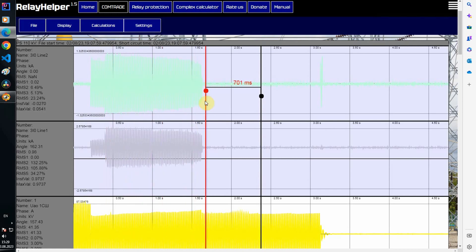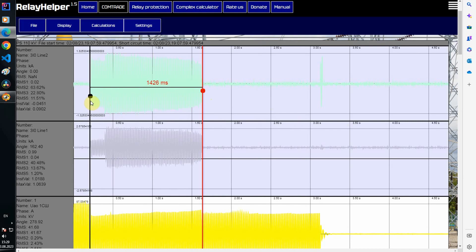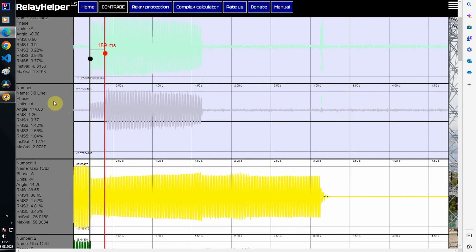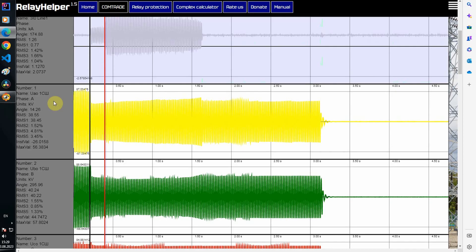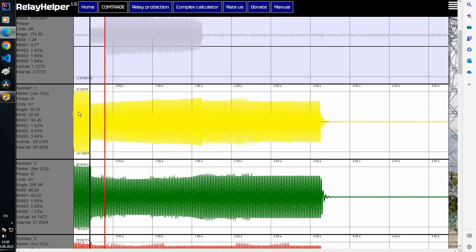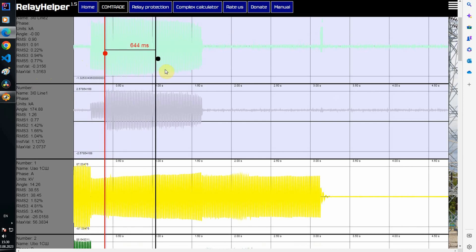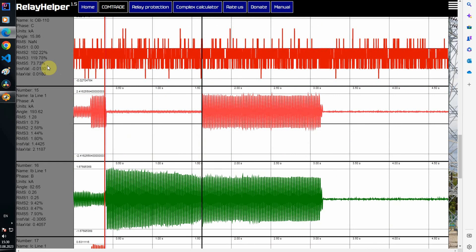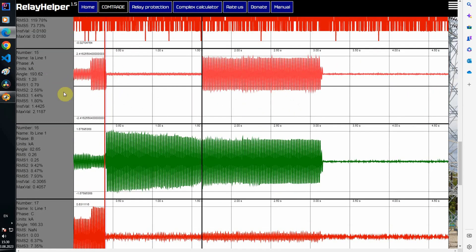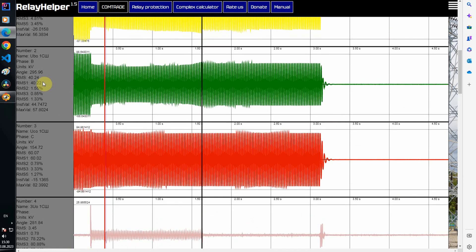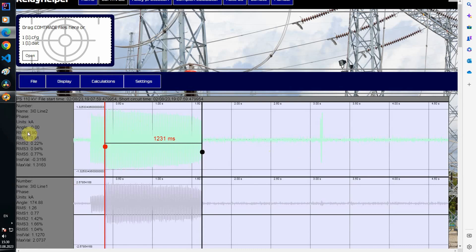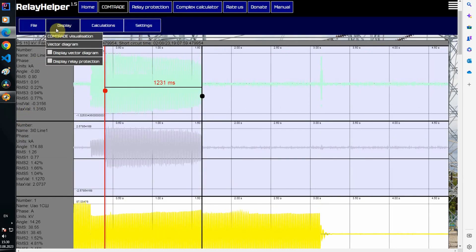As you can see, at first a short circuit was with earth, then without. Now we can divide the event into three sections. The first section lasts until one of the lines is tripped from the power side. The second section with a single phase short circuit on another phase. In the third section we see a two-phase short circuit without earth. There is no zero sequence current here. Let's look at the vector diagram.